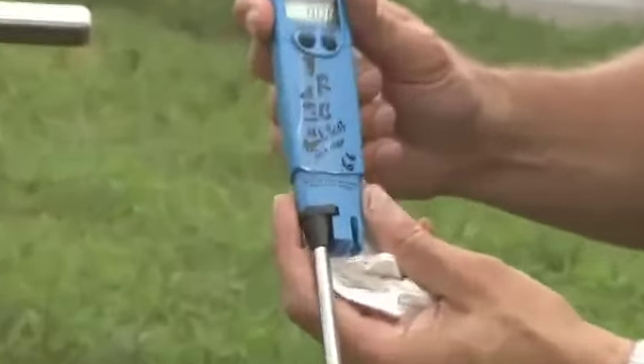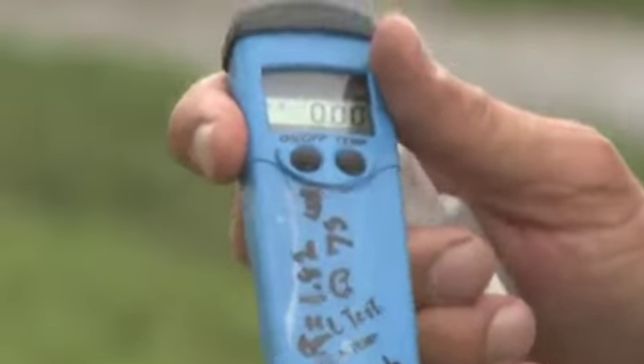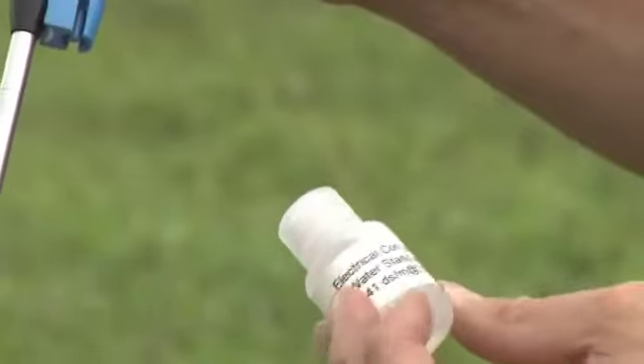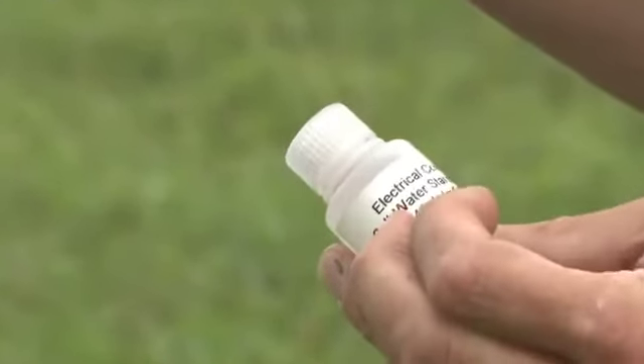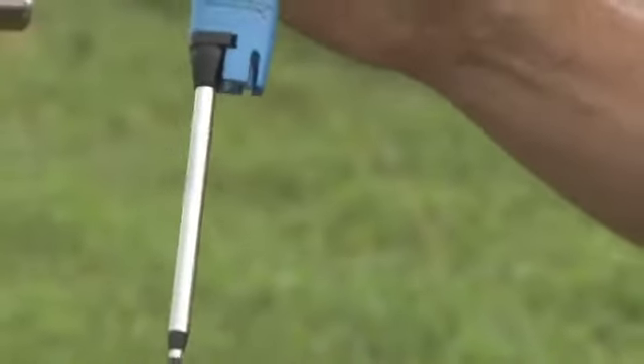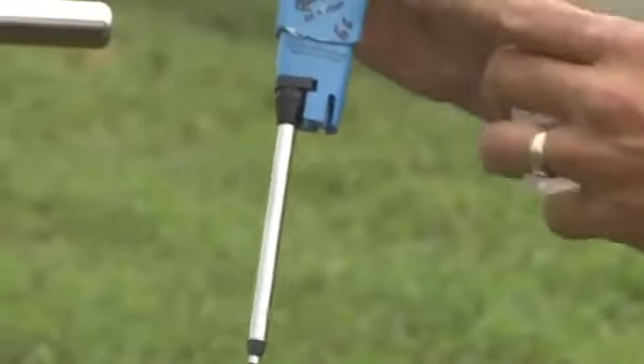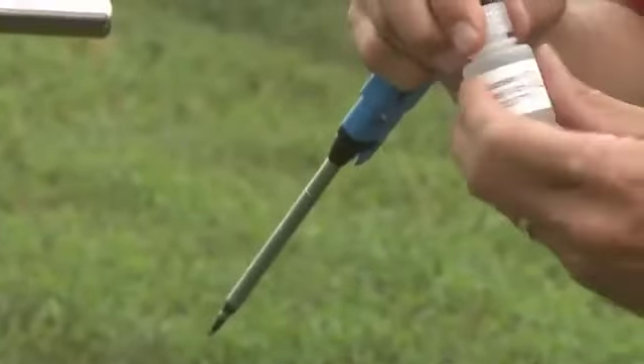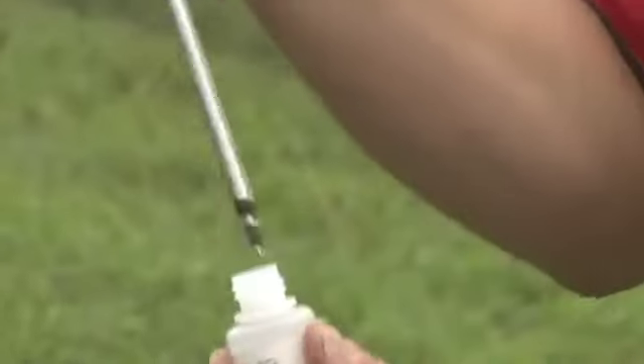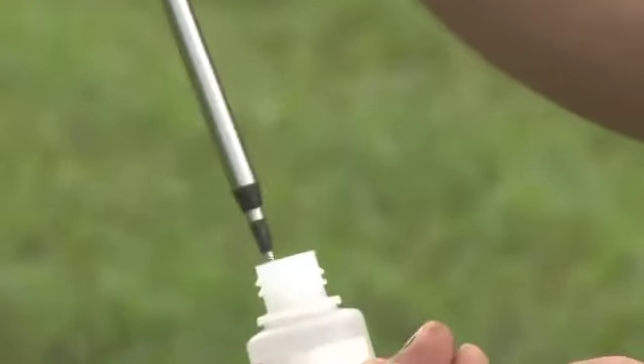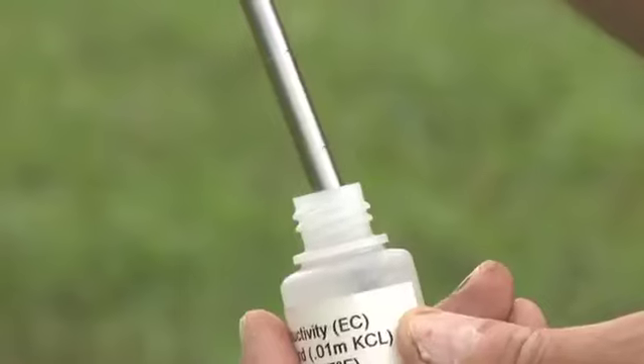If we need to recalibrate, each of you should have received an EC standard, water standard, 1.41 decisiemens. What we would do before we do that is make sure it's good and rinsed off. Clean it off. Ideally, you would do this in room temperature. In this example, it was near 73 degrees. So we would take the top off of this, and then we're going to hold it without touching the sides of the bottle.